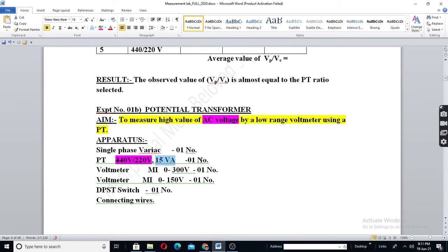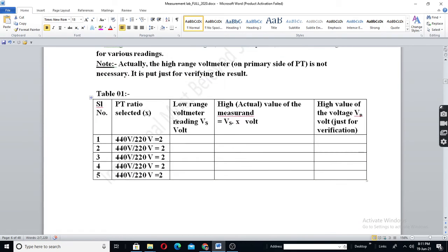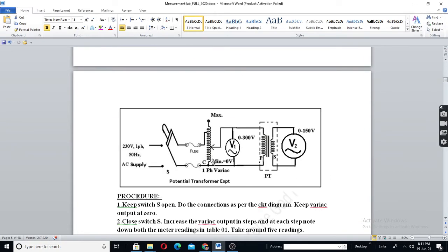Now, how to measure? See, initially we will keep variac output at zero. You can see the table here. As we increase the output of variac, voltage applied to the potential transformer will also increase. Forget V1. There is no need of V1 in the experiment. Because, V1 will be high voltage. We are measuring V1 with the help of V2 and PT ratio.